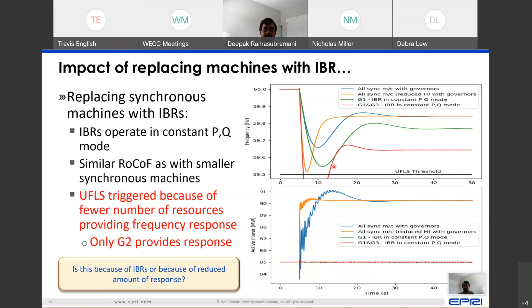So the question we may ask is, is the triggering of UFLS because there are inverter-based resources in the system which have replaced machines, or is it because there is a reduced number of sources providing frequency response itself? If you switch off governors in a synchronous machine system, you will start getting a similar response where UFLS is triggered, wherein the number of resources providing frequency response has reduced, which means you can still have a chance of UFLS triggering. Yes, it is a few seconds later, but the number of resources providing this frequency response really matters and plays a more crucial role than the way in which the frequency response is obtained from either synchronous machines or inverter-based resources.